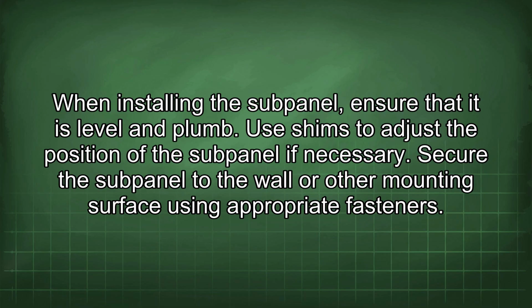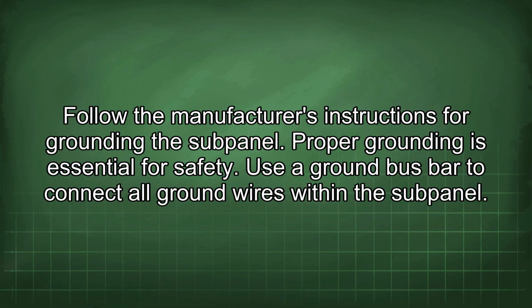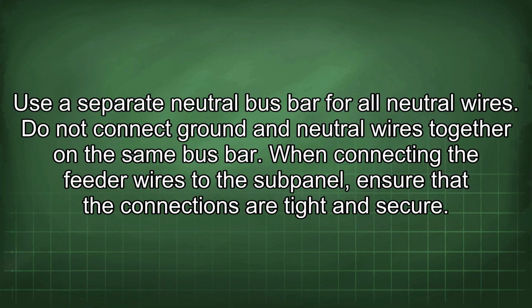When installing the subpanel, ensure that it is level and plumb. Use shims to adjust the position of the subpanel if necessary. Secure the subpanel to the wall or other mounting surface using appropriate fasteners. Follow the manufacturer's instructions for grounding the subpanel. Proper grounding is essential for safety. Use a ground bus bar to connect all ground wires within the subpanel. Use a separate neutral bus bar for all neutral wires. Do not connect ground and neutral wires together on the same bus bar.